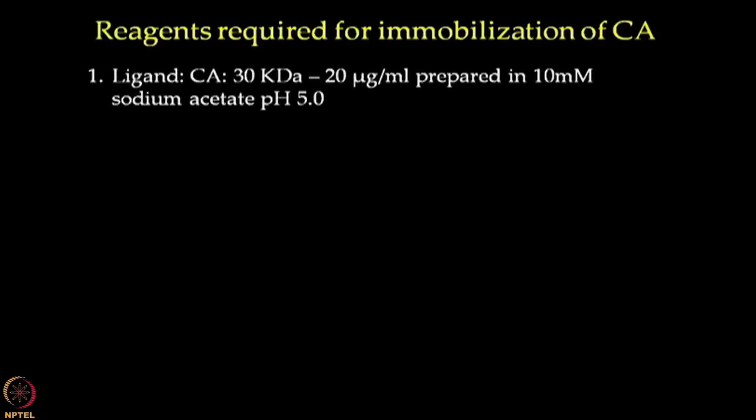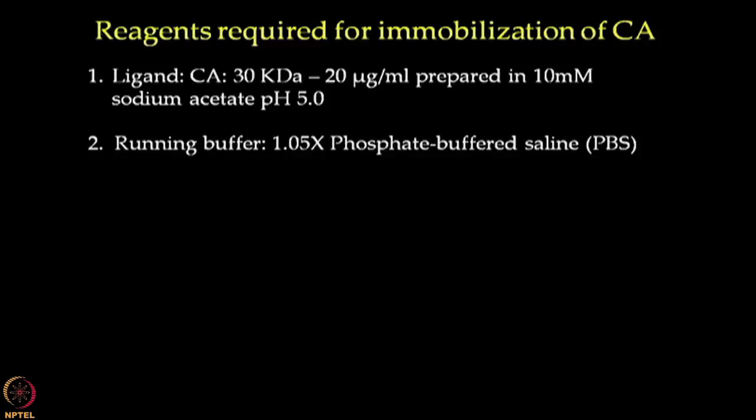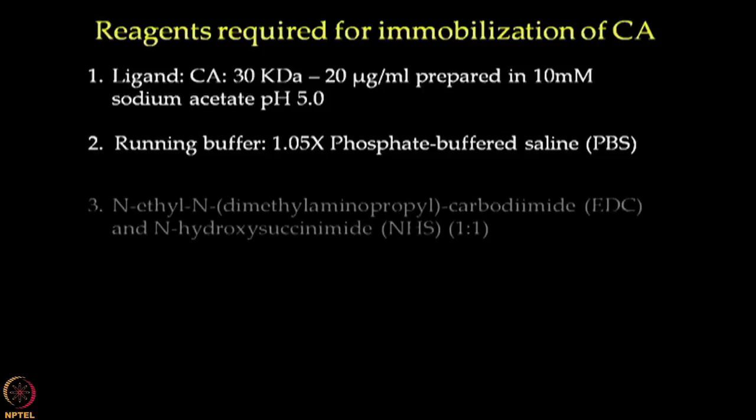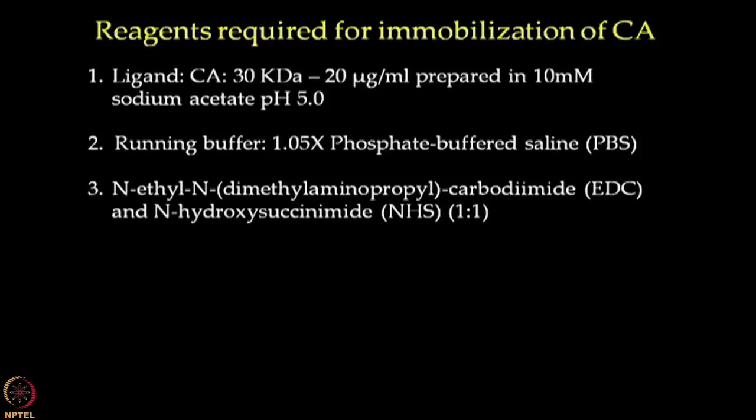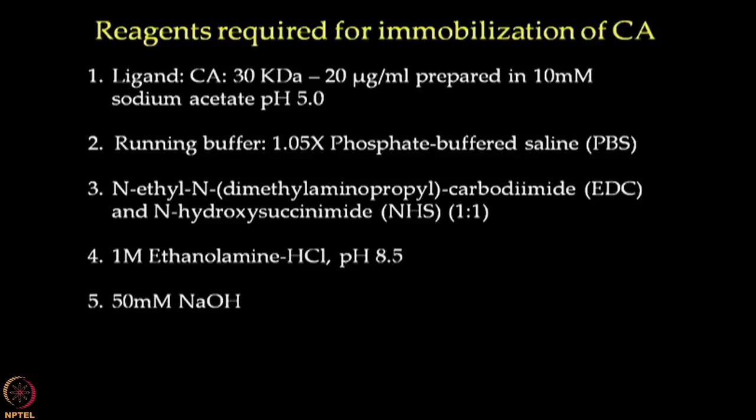As per the volume listed on the table, we will prepare the buffers and reagents required for immobilization of carbonic anhydrase on the sensor chip. The ligand is prepared at a working concentration of 20 microgram per ml using an immobilization buffer of 10 millimolar sodium acetate pH 5. We will be using 1.05x PBS buffer as the running buffer which will be connected to the system followed by priming. EDC and NHS are prepared as suggested in the amine coupling kit for surface activation. 1 molar ethanolamine HCl pH 8.5 is prepared for blocking the free ester groups on the surface. Lastly, 50 millimolar NaOH was prepared which will be used to remove the electrostatically bound ligand.